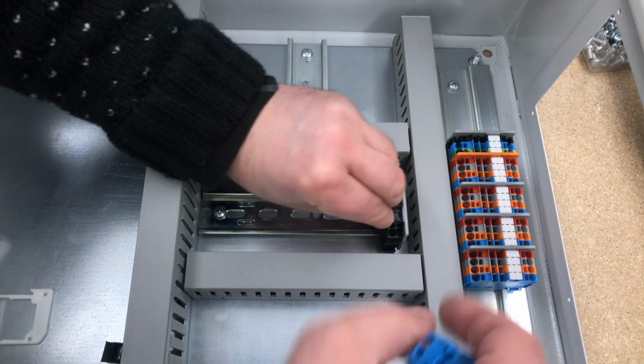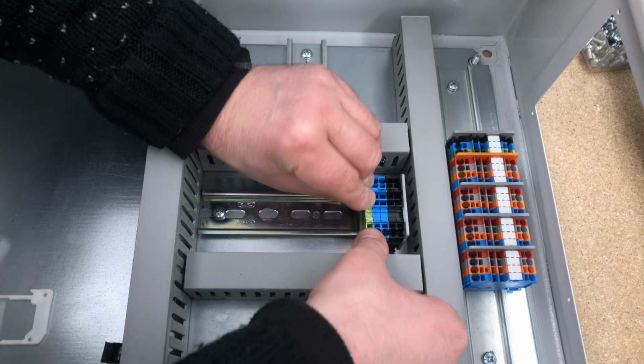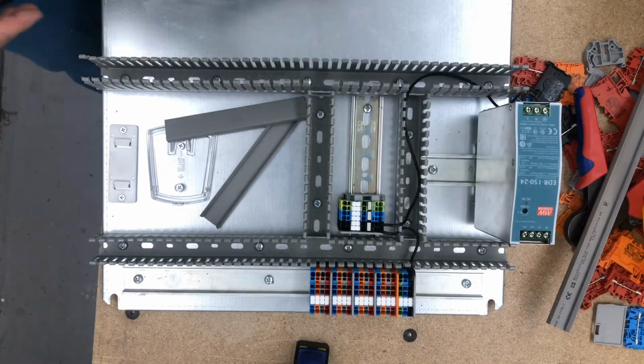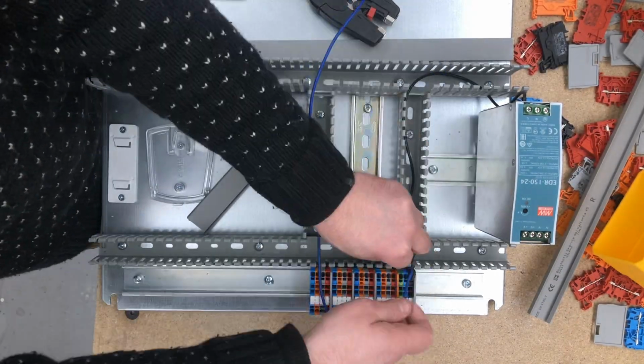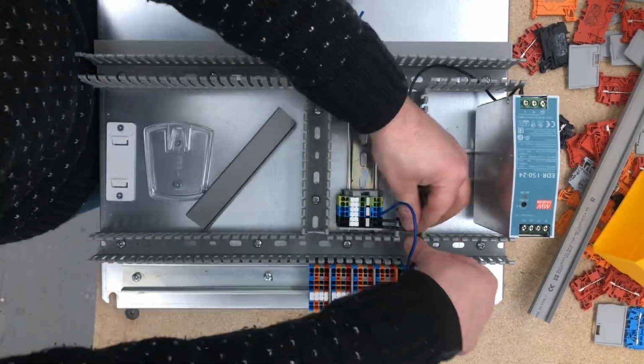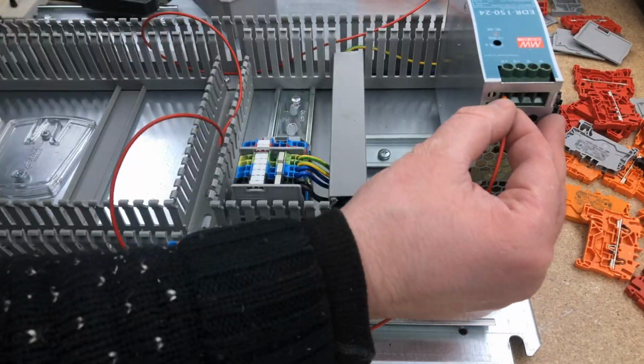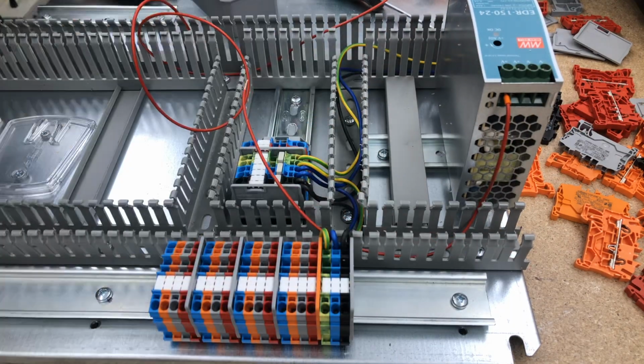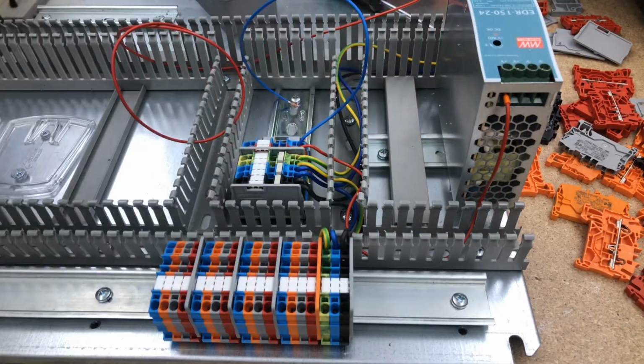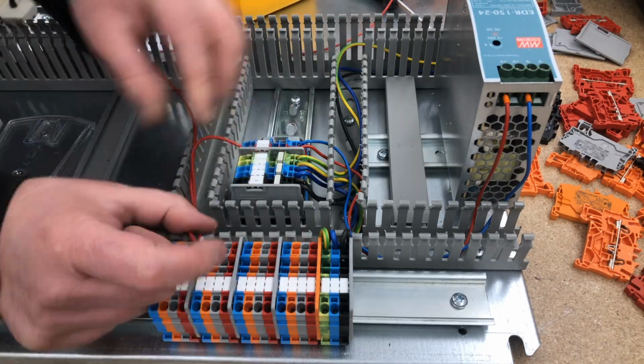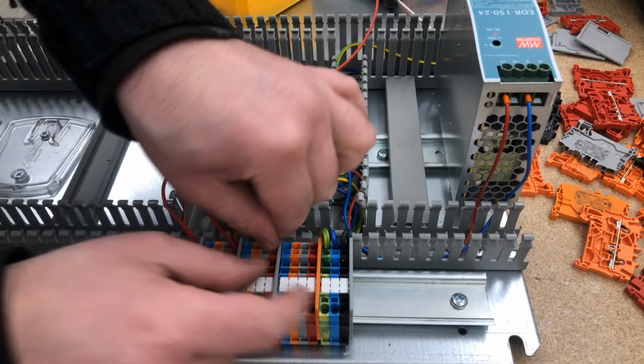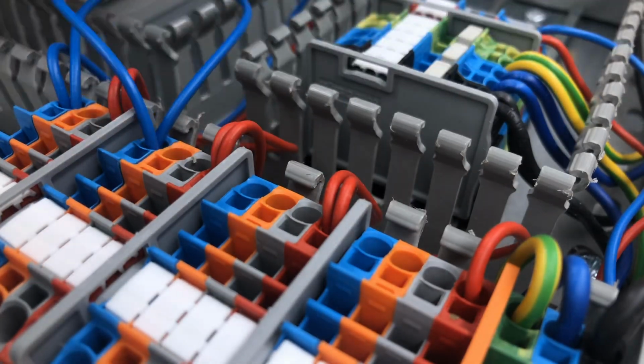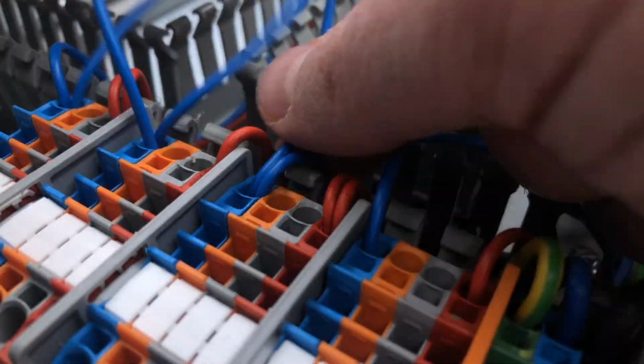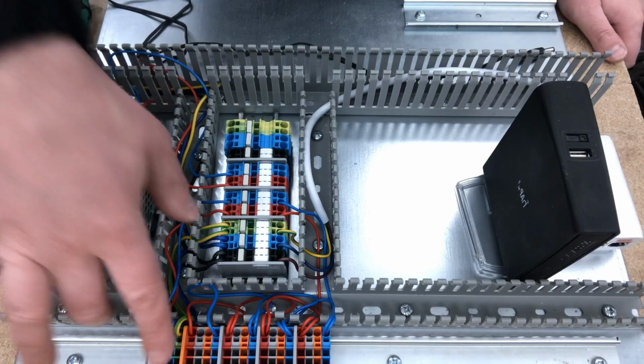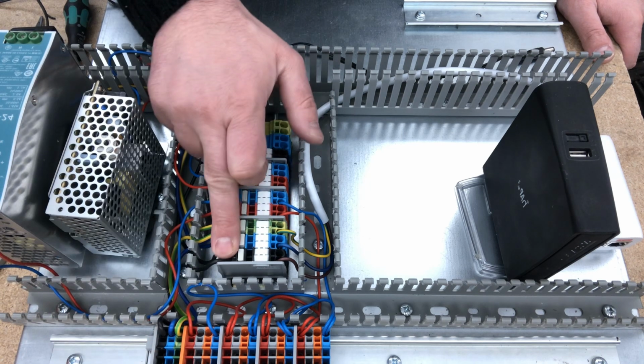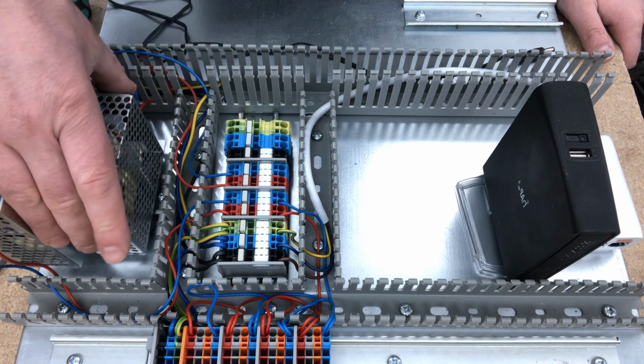This section further down in the control panel is for distribution of the power. So I'm wiring all this stuff together, and I have the 24 volt power supply also in place, and I'm wiring the output of it to these input terminals so I can distribute the 24 volts to all my devices in the flat. So I took the 230 volts and I go to this set of terminals.